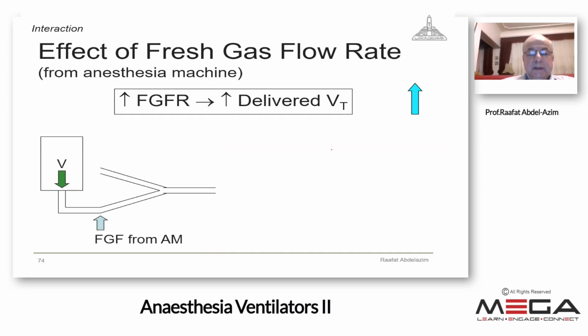Effect of fresh gas flow means that, as I said before, the ventilator is giving the preset tidal volume to the patient through the inspiratory limb. At a certain point, the fresh gas flow will join the output of the ventilator and will go together into the patient through the inspiratory limb. But not all the fresh gas flow. The fresh gas flow is giving its output during the whole time, but it is only allowed to go inside the inspiratory limb during the inspiratory time. During expiration, the fresh gas flow will go into the spill valve. So part of the fresh gas flow will go into the inspiratory limb during the inspiratory time only.